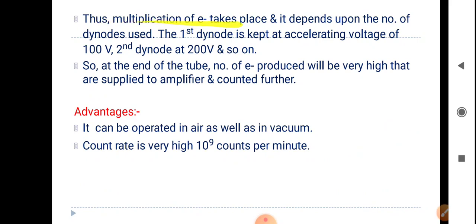Thus, multiplication of electrons takes place and it depends on the number of dynodes used. The first dynode is kept at accelerating voltage of 100 volts, second dynode at 200 volts, and so on. So at the end of the tube, the number of electrons produced will be very high, which are supplied to the amplifier and counted further.